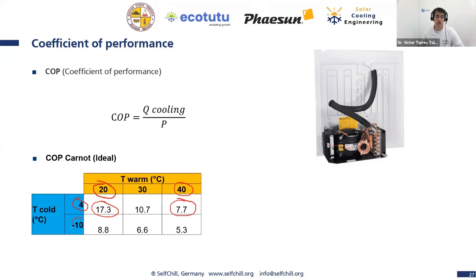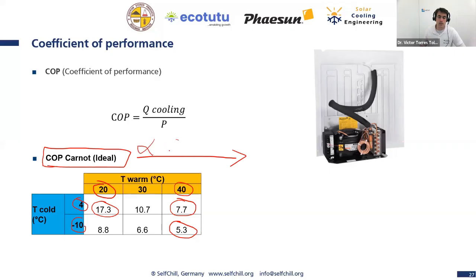What about if I go from 40 degrees to minus 10 degrees? With the Carnot equation, which is the maximum you can get, it is still 5.3, so 500%. I invest 1 kilowatt hour and get 5 kilowatt hours of cooling energy. But remember, this is the ideal COP, so the maximum. To get to the real one, we use the ideality factor, which is around 25%, at least for our self-chill cooling unit.